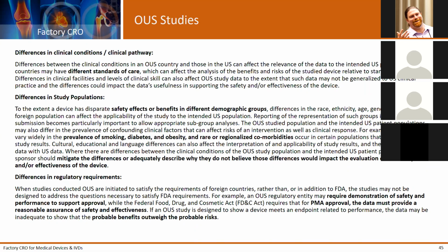And the FDA has made a shift from substantial equivalence used to mean it has the same intended use. Now it means it must have the same indications for use. And they're saying, any differences in indication for use, we're not saying you can't get substantial equivalence. We're saying the burden of proof that it is substantial equivalence has become much tougher now. So now they're pushing companies to show more clinical data, more human factors data to prove that those minor differences in indications are still safe. That's a major shift that I've seen recently.